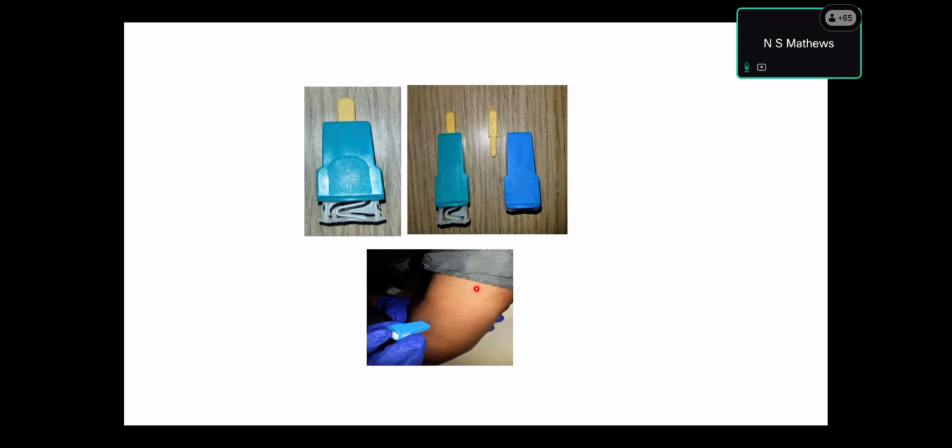The other thing is you don't have to make 3 stab wounds, because there is only one type of wound you can get with this because of the trigger, and we expect it to be a stab wound. The other thing is the edge of this has some counter irritant, irregular surface which gives a counter irritant effect so that the actual stab is not felt. So it is a little more patient compliant as well. So fewer wounds, less pain, much more user friendly and patient friendly.